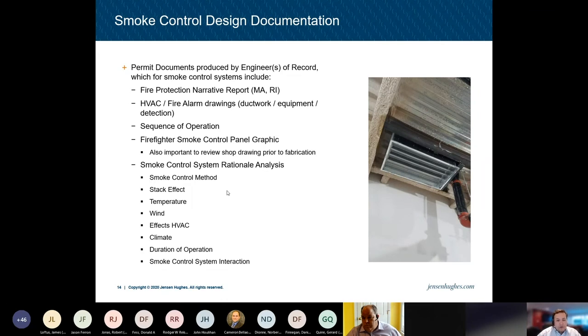Obviously, the HVAC and fire alarm drawings are crucial to have a ductwork layout, equipment layout, the detection. There's the sequence of operation, which either could be on the fire alarm drawings or the HVAC, depending on what's controlling that system. There's a graphic layout of the smoke control panel, so you want the engineer to provide that and dictate how the panel is supposed to look. That then is utilized by a vendor such as Space Age, who produce a shop drawings for that. And then it's important that gets reviewed, not only by the engineer of record, but also the fire department prior to fabrication. So there's no issues when it gets installed out in the field and it's getting tested for final.